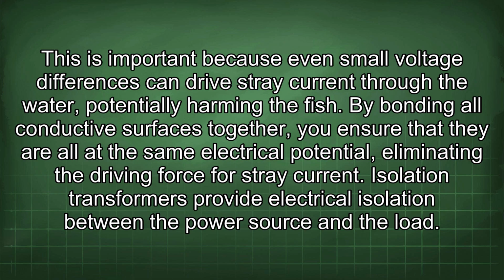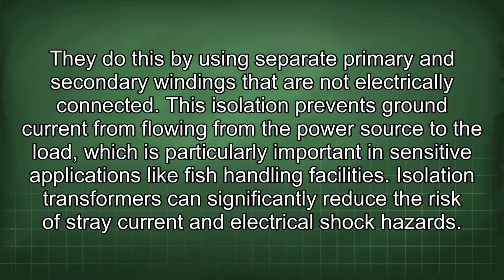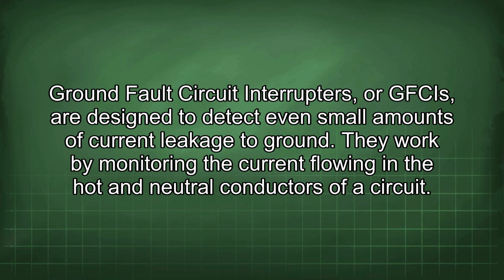Isolation transformers provide electrical isolation between the power source and the load. They do this by using separate primary and secondary windings that are not electrically connected. This isolation prevents ground current from flowing from the power source to the load, which is particularly important in sensitive applications like fish handling facilities. Isolation transformers can significantly reduce the risk of stray current and electrical shock hazards. Ground fault circuit interrupters, or GFCIs, are designed to detect even small amounts of current leakage to ground.